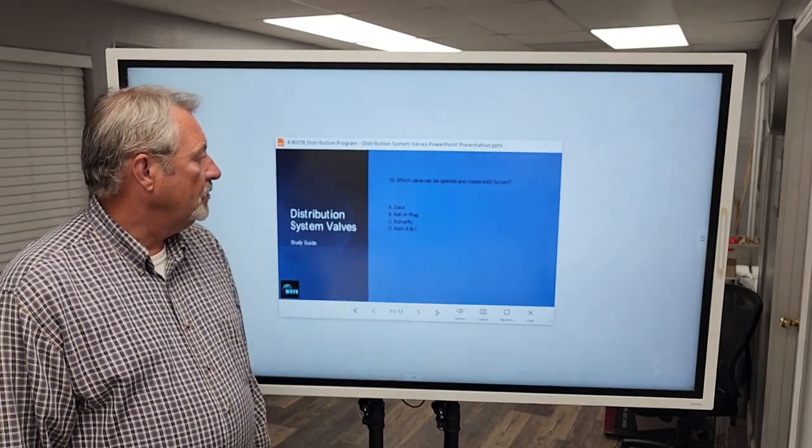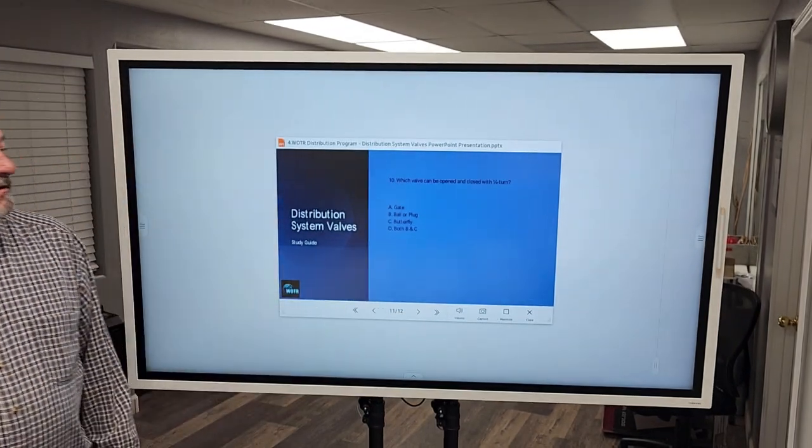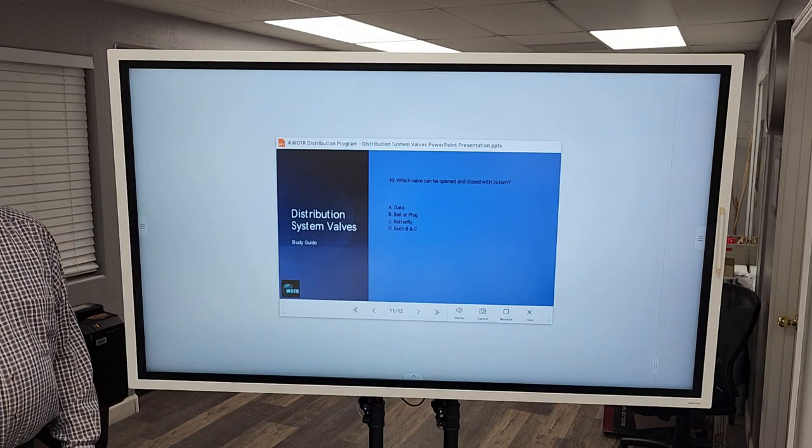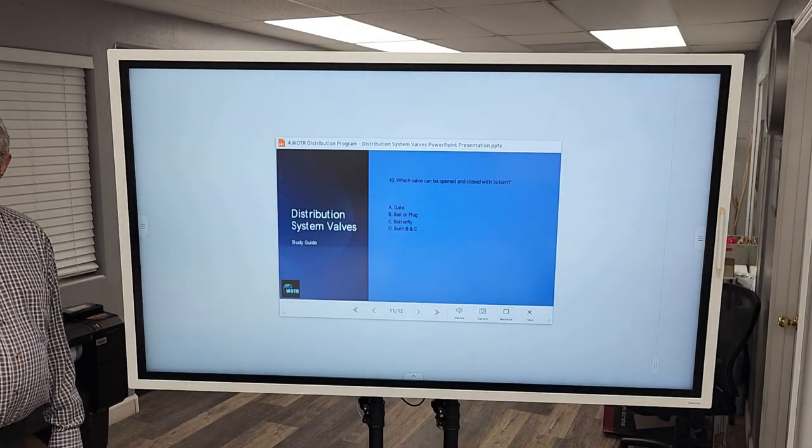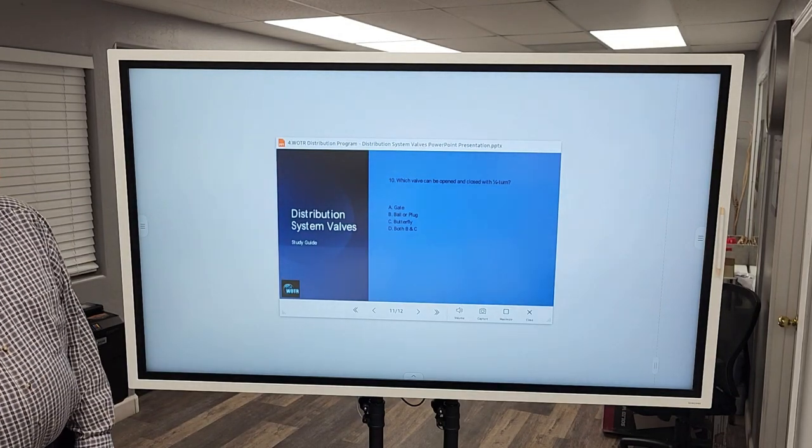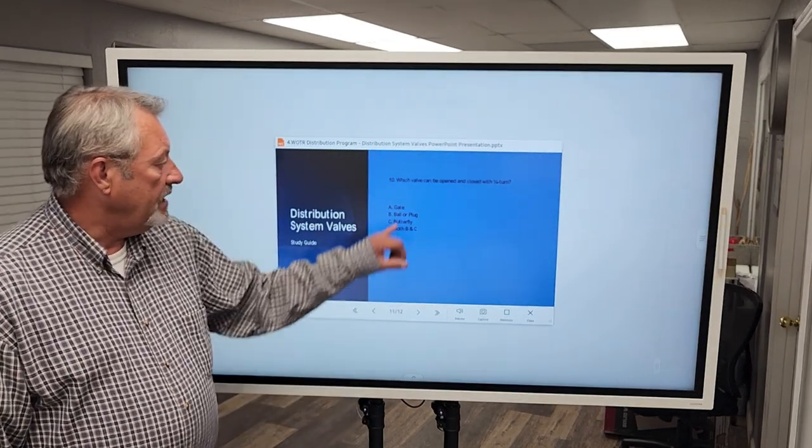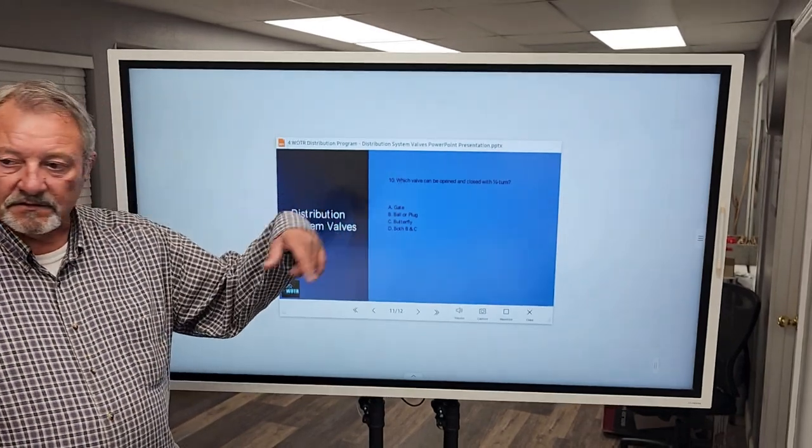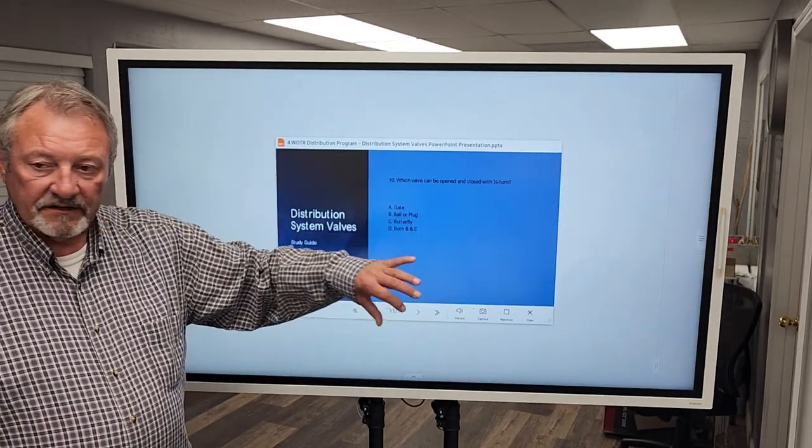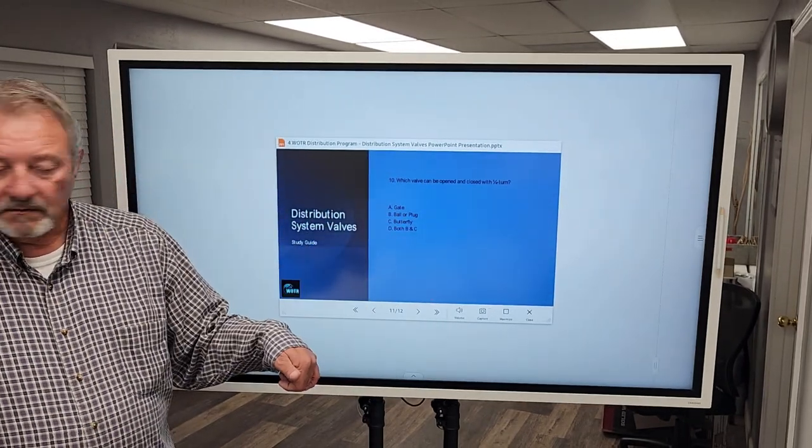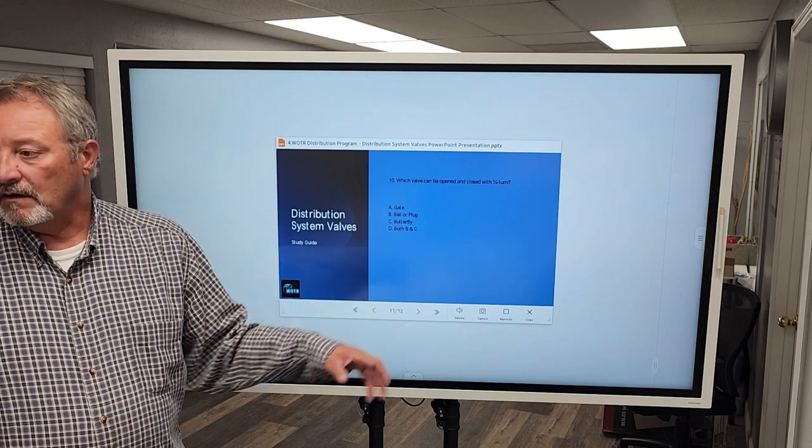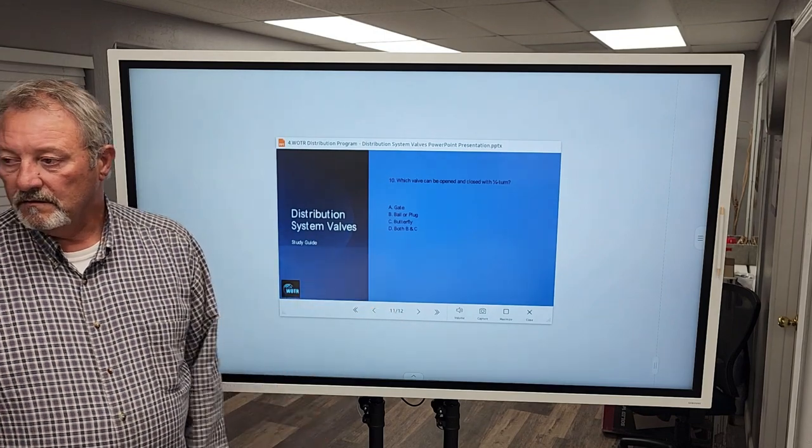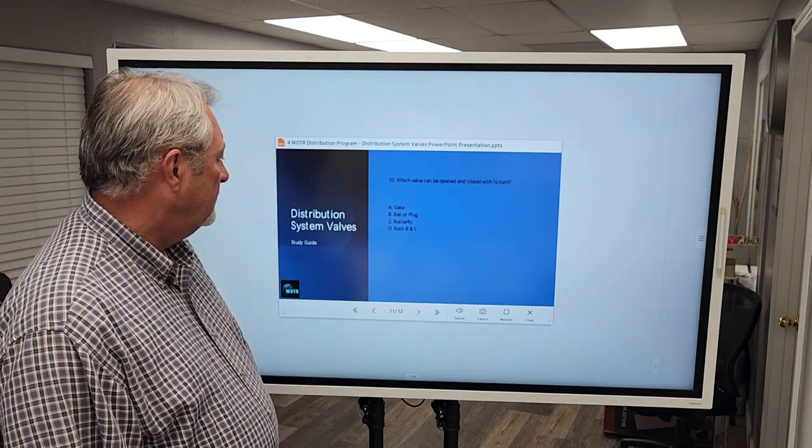Number 10. Which valve can be opened and closed with a quarter turn? B and C. So a gate valve takes several turns. Ball or plug valve, that's a quarter turn. Butterfly valve, a quarter turn. Very good.